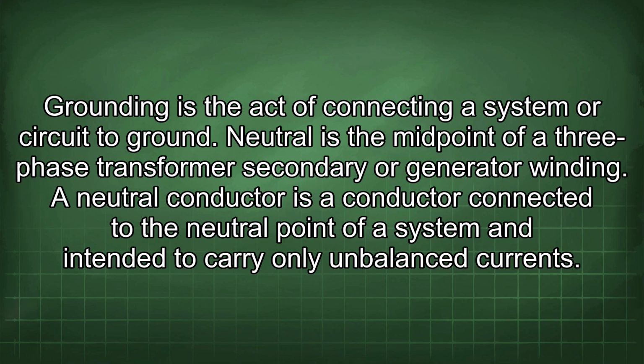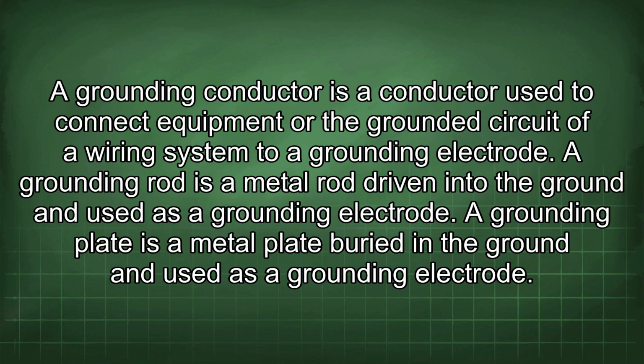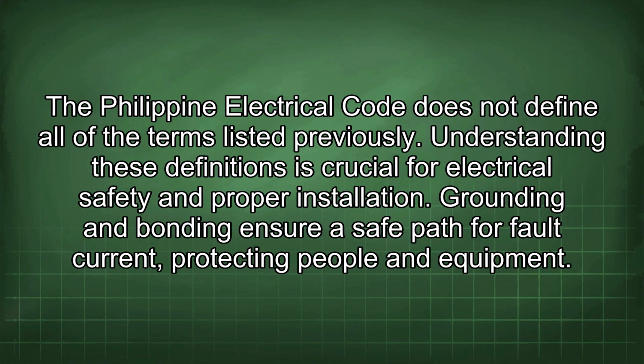Neutral is the midpoint of a three-phase transformer secondary or generator winding. A neutral conductor is a conductor connected to the neutral point of a system and intended to carry only unbalanced currents. A grounding conductor is a conductor used to connect equipment or the grounded circuit of a wiring system to a grounding electrode. A grounding rod is a metal rod driven into the ground and used as a grounding electrode. A grounding plate is a metal plate buried in the ground and used as a grounding electrode. The Philippine Electrical Code does not define all of the terms listed previously.